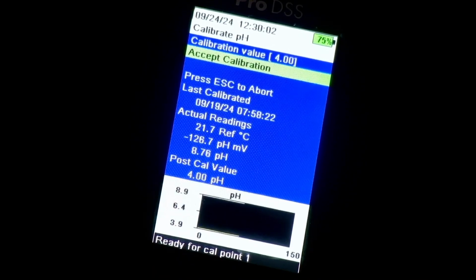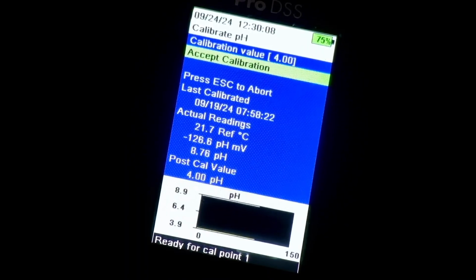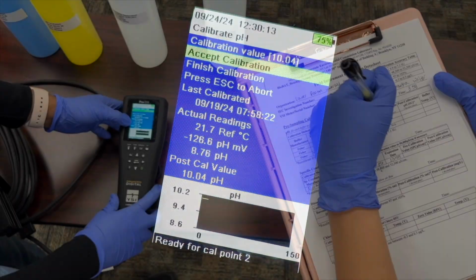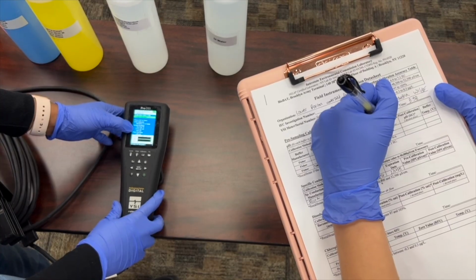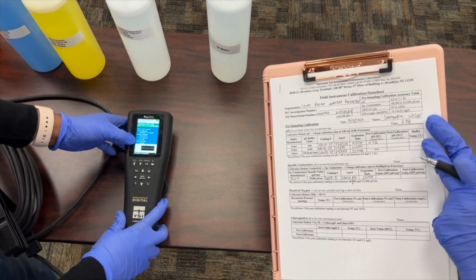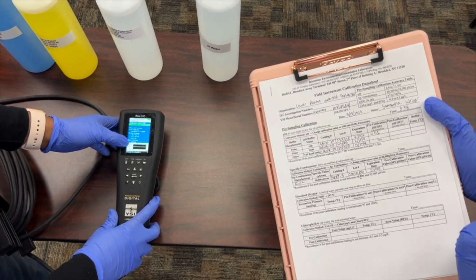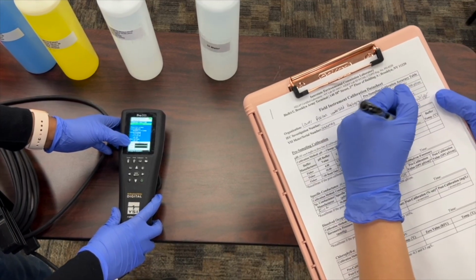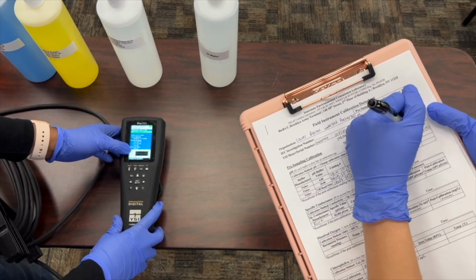Select Accept Calibration and wait for the message Calibrating Sensor to pop up. Now, it should say ready for cal point 2 at the bottom of the screen, meaning you can move on to your next buffer. Be careful not to press the Accept option more than once, or it will move on to the cal point 3 and you will have to discard and redo the calibration.